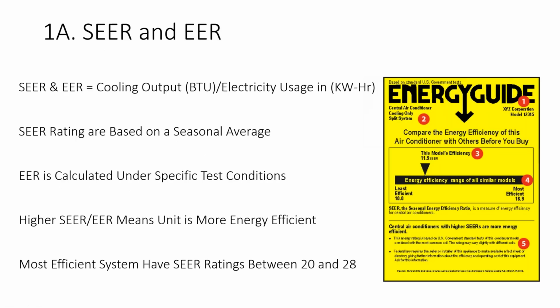In North America, SEER and EER are the most used efficiency units, and all air conditioning units in the North American industry have SEER or EER ratings on them. SEER and EER are quite the same in that the formula to derive the efficiency is the same: cooling output in BTU divided by electricity usage in kilowatt hours. The difference is in how we get the average. SEER is a season-based average, while EER is a spot average, mostly calculated under very specific conditions, usually in test labs. Higher SEER and EER means your unit is more efficient.